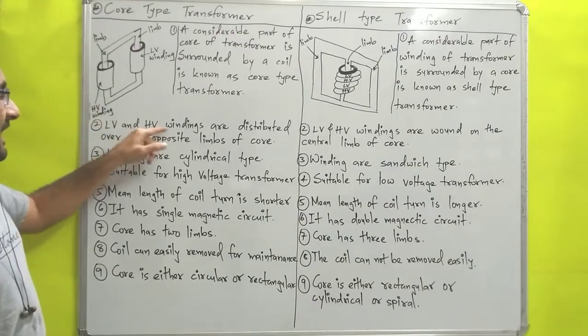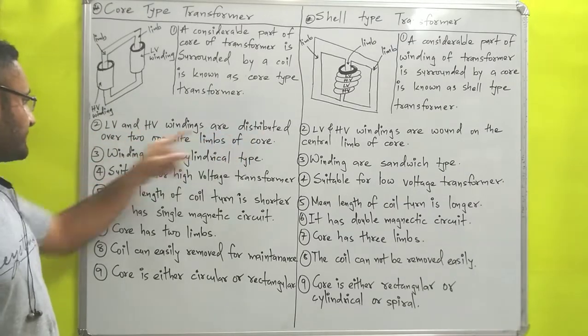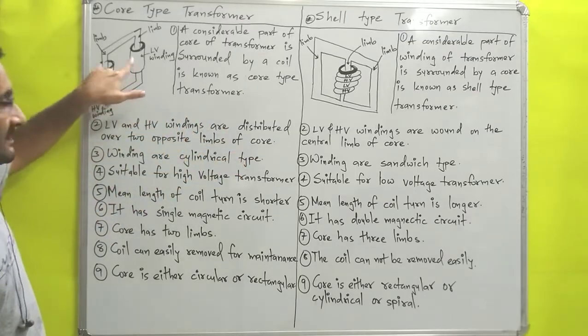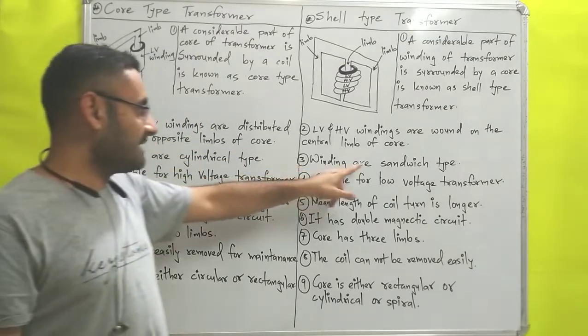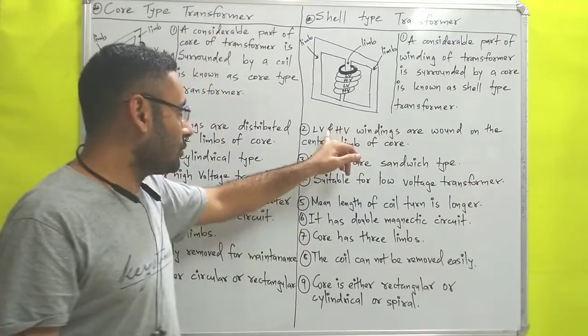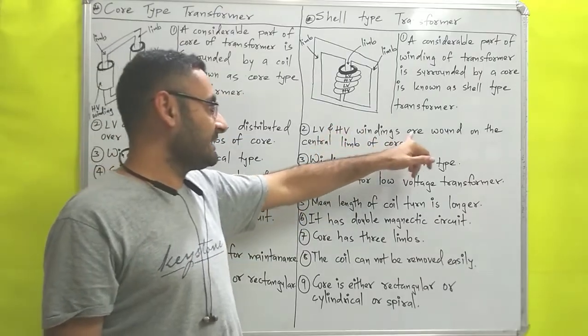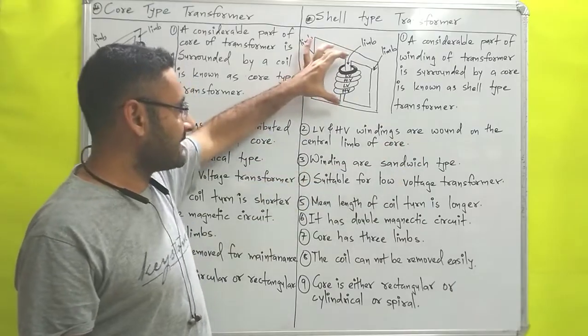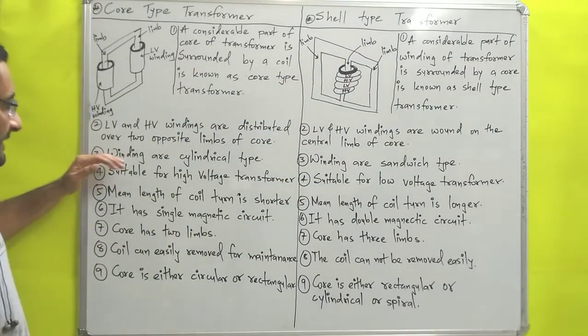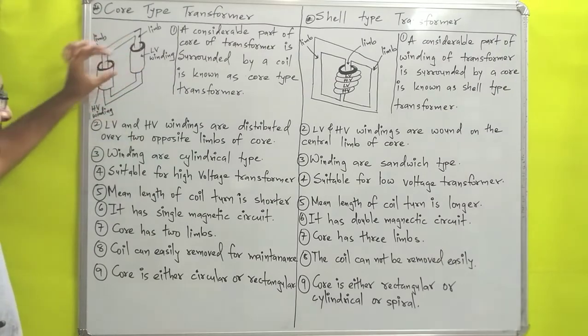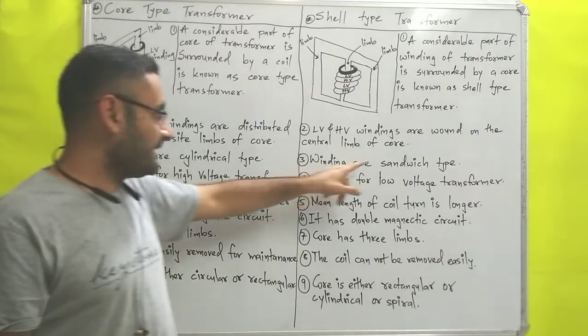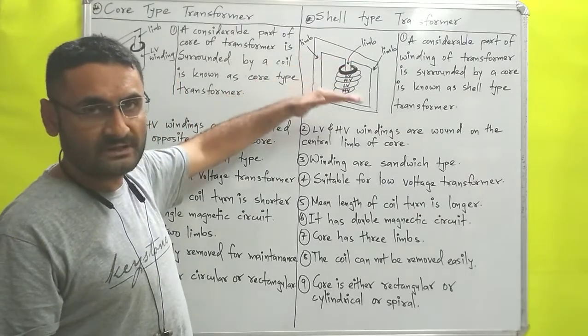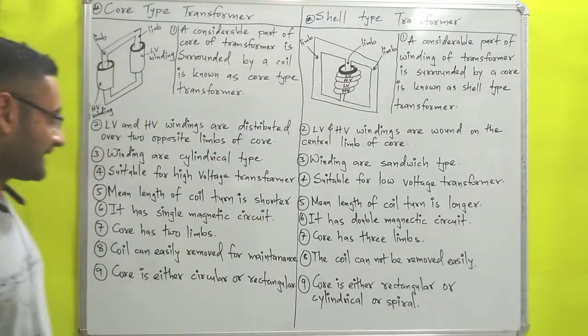The next difference is that in the core type, the low voltage and high voltage windings are distributed over two opposite limbs of the core, as you can see from the figure. In the shell type, the low voltage and high voltage windings are wound on the central limb of the core. The windings in core type are cylindrical type, while in shell type the windings are sandwiched — one after another: low voltage, high voltage, low voltage, high voltage.